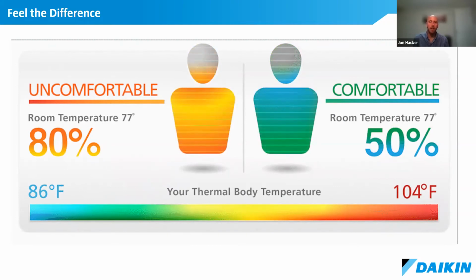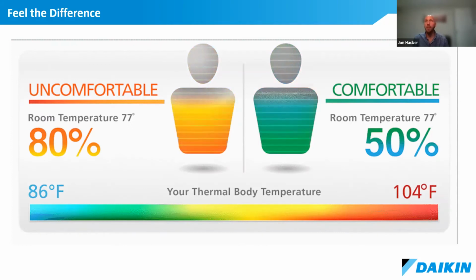All right, so there's a very typical problem with HVAC equipment. Maybe it's a cooling system and maybe it's oversized and it will short cycle significantly. And when air conditioning equipment short cycles, it doesn't appropriately remove the relative humidity in the air. It does drop the temperature, but it doesn't drop the relative humidity. And in the scenario that we're showing here, the room temperature, maybe the set point is 77 degrees, but if that equipment is oversized and it's short cycling, relative humidity may stay at 80%. And at that temperature, 80% relative humidity, most humans are going to be pretty uncomfortable.